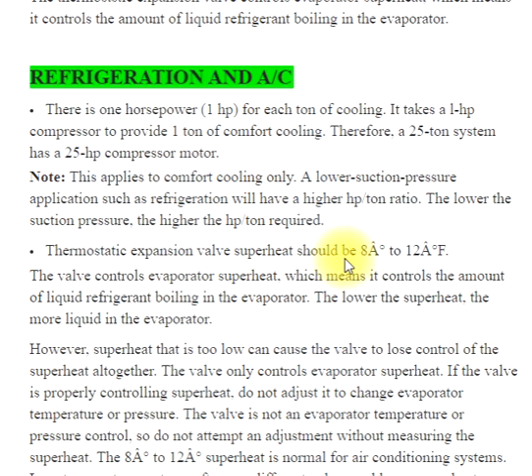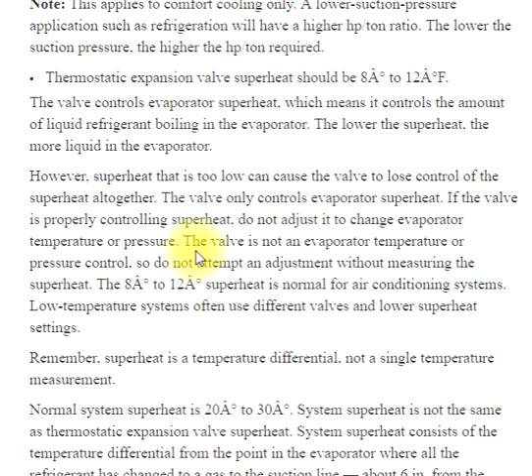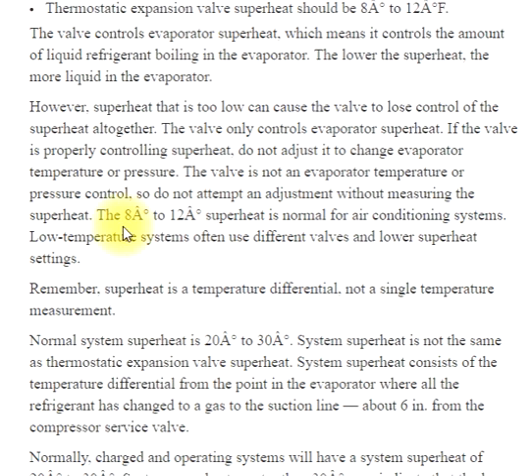Thermostatic expansion valve superheat should be 8° to 12°F. The valve controls evaporator superheat, which means it controls the amount of liquid refrigerant boiling in the evaporator. The lower the superheat, the more liquid in the evaporator. However, superheat that is too low can cause the valve to lose control of the superheat altogether. The valve only controls evaporator superheat — do not adjust it to change evaporator temperature or pressure without first measuring the superheat.